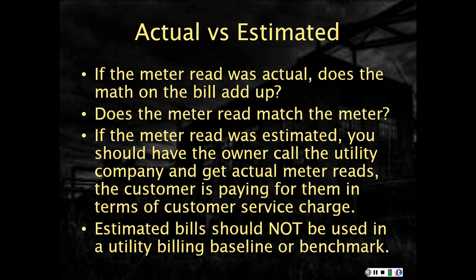So again, actual versus estimated. If the meter read was actual, does the math on the bill add up? Does the meter read match the meter? If the meter read was estimated, you should have the owner call the utility company. We just talked about that. Estimated bills should not be used in a utility baseline or benchmark. So it's sort of a review or a summary of what we just talked about.